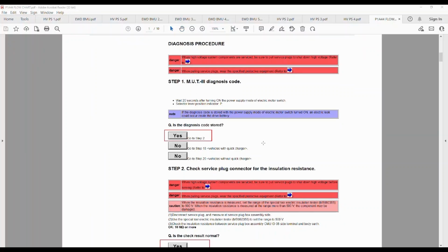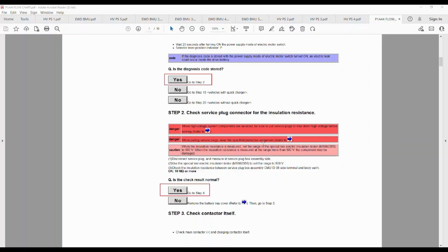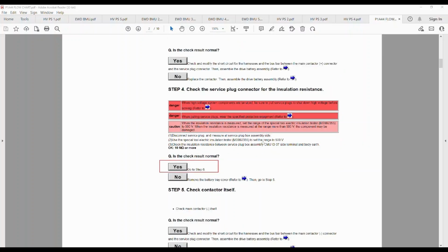Moving on to step two then, it is insulation test inside the battery. So what we're going to do here is remove the service plug. Follow the instructions here. It wants us to insulation test inside the battery at 500 volts. So it's important we set the tester accordingly. Gloves on at this point, and well, let's have a look at the results.